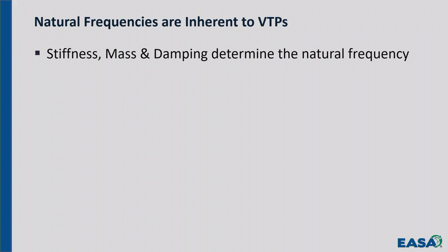The most common, probably the only resonance mode that you need to worry about with vertical turbine pumps and motors is what we call the reed frequency, which is when something is standing up or down and vibrates unrestrained on one end. That's different than being restrained on both ends, as is a horizontal rotor with a mass in the middle. It has a natural resonant frequency, but that's not a reed frequency. This standing up here and vibrating back and forth like a tuning fork is a reed frequency. The first means it's just bending back and forth. The second means that it's actually going into an S kind of a curve.